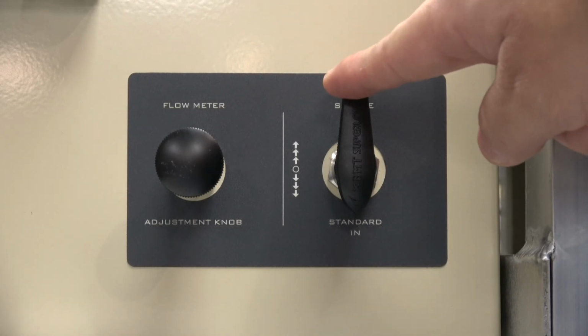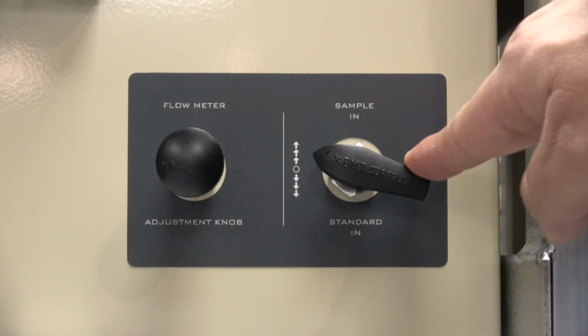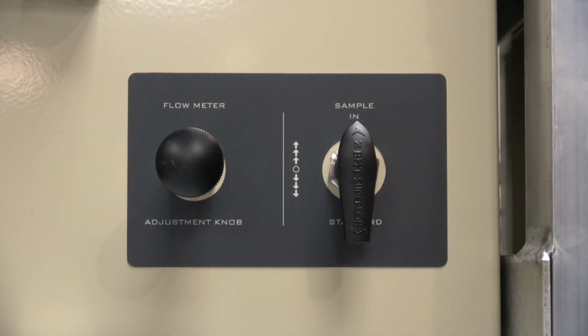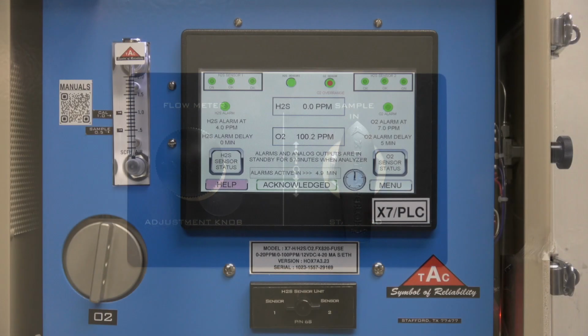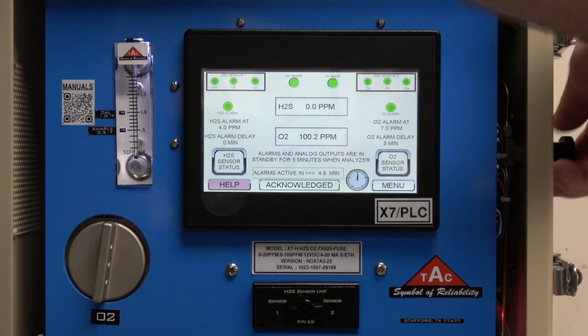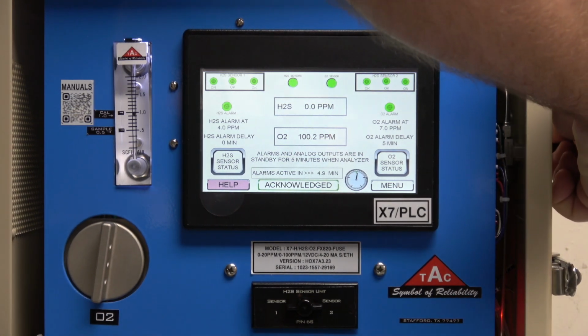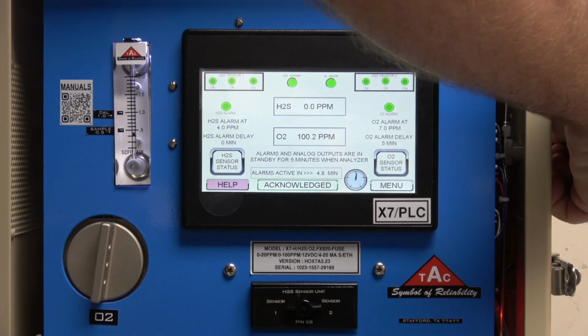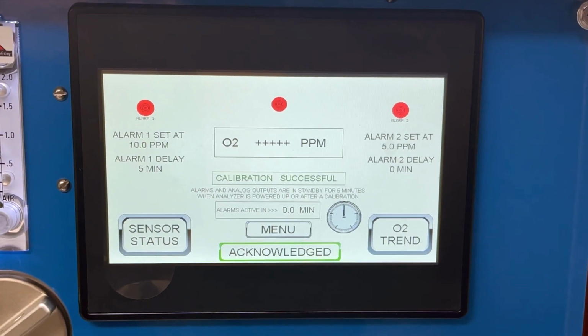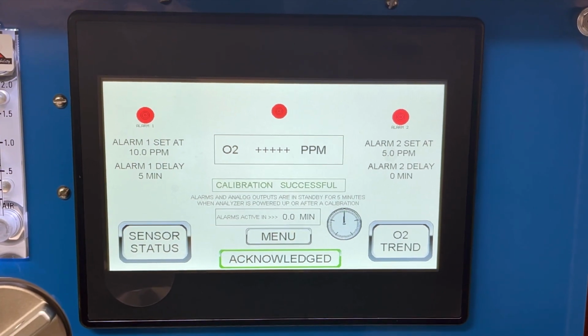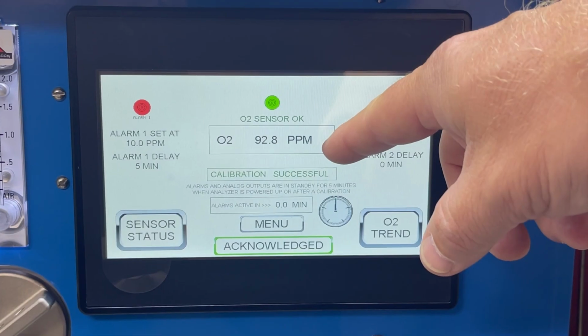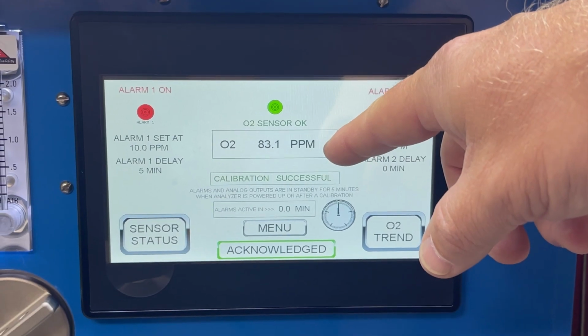Turn the manual cal valve on the side of the enclosure from standard in to sample in. Verify flow meter on the front panel is set to 0.5. The controller display will read 4+ signs until the O2 levels are less than 100 ppm.